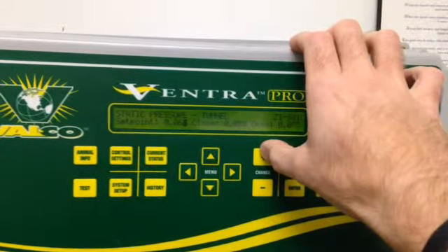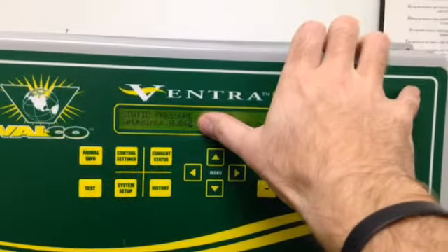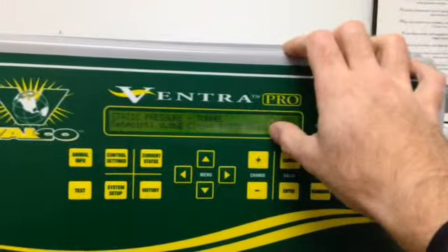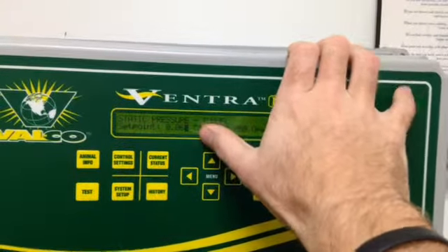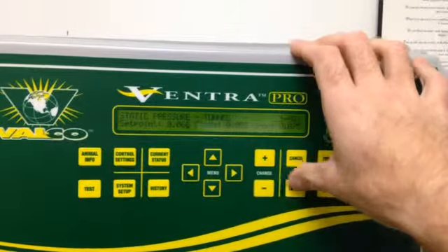You might consider a higher number for a wider barn, because this determines the velocity of the air coming in through the inlet and how far towards the center of the barn it's going to come before turning to go down the barn in tunnel mode. You don't want it to be too terribly high, because that will cause the fans to work harder than they need to be able to move the air that they must.